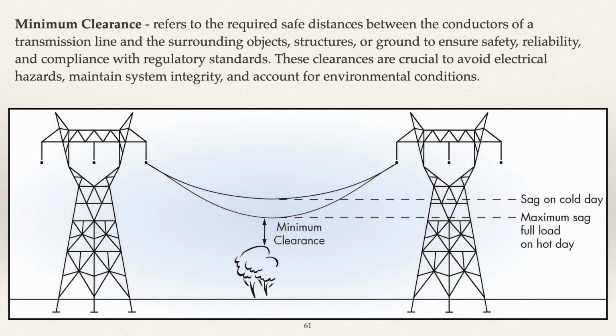Minimum clearance refers to the required safe distances between the conductors of a transmission line and the surrounding objects, structures, or ground to ensure safety, reliability, and compliance with regulatory standards. These clearances are crucial to avoid electrical hazards, maintain system integrity, and account for environmental conditions.